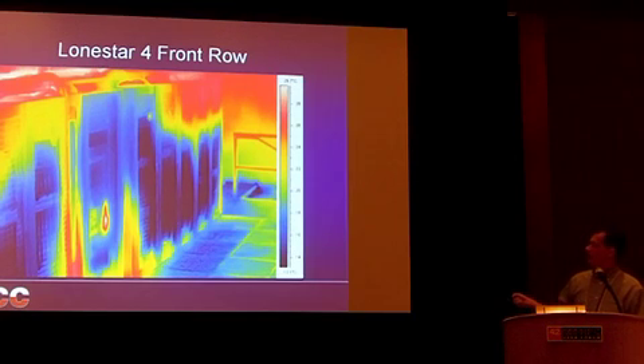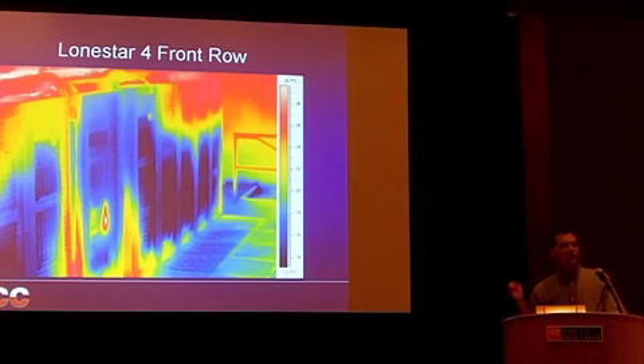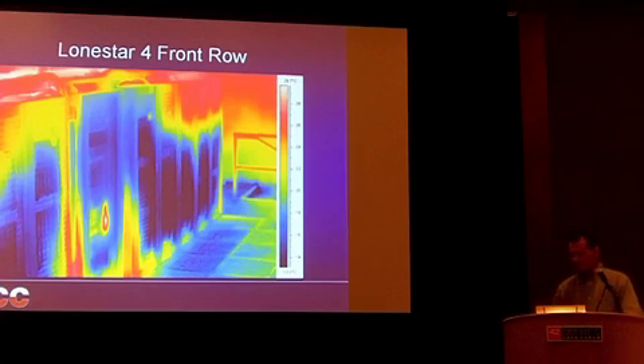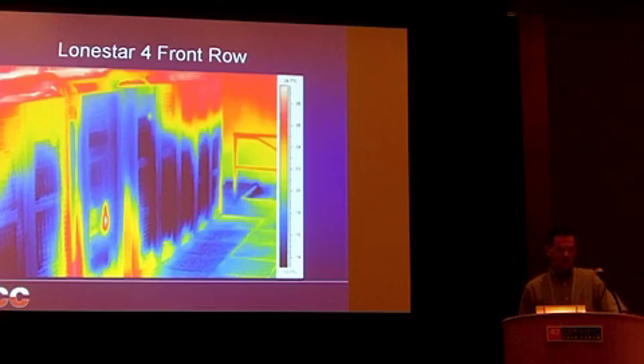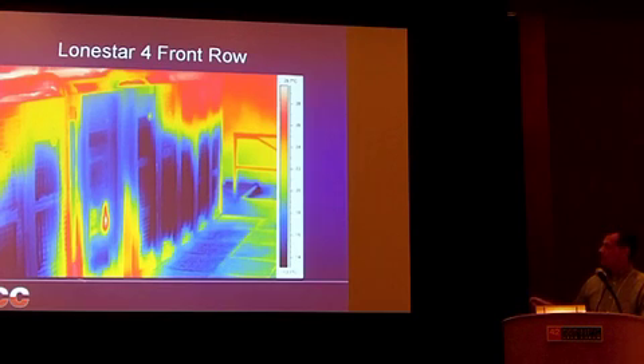But what really caught our eye was this red spot here at the front of the switch rack. It turned out that some of the fans in the switch rack weren't running right, and there was a firmware bug that Mellanox had to fix. And we actually had hot air coming out of the front of the switch. Again, this is something we never felt, never knew it was there or anything until we actually did the thermal imaging. It was just an interesting side effect that when we were looking at all the equipment and everything. The other thing is you notice there's some bleed through between the gap where the switch rack is.